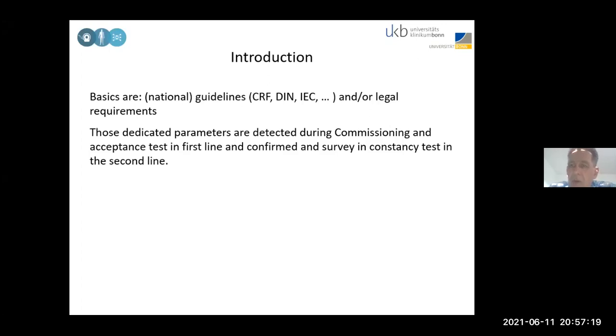And after the commissioning, you have to say: these are the parameters which need to be set and observed. What do I then do? I have to do a quality control of those parameters and properties, and that's called constancy checks or constancy tests. They're usually second line. So everything starts with the acceptance and the commissioning. I always recommend, if you get a new machine, speak with the vendor and tell the vendor what you are going to use this machine for. Do you do standard work, or do you have special requirements? These could be set up in the acceptance test or in the commissioning, so that you can observe those parameters over the year, over half a year, or even a decade.